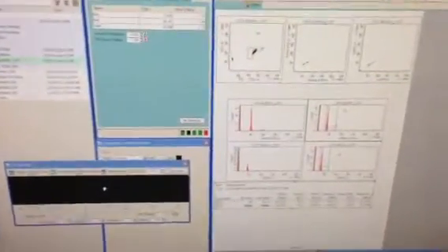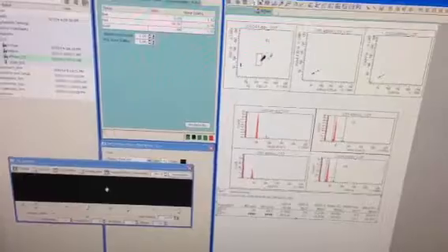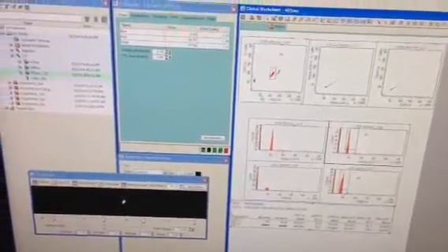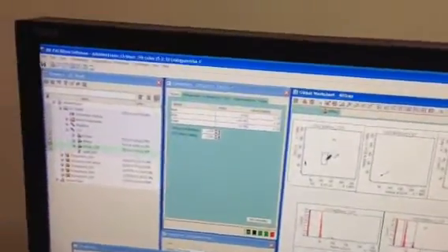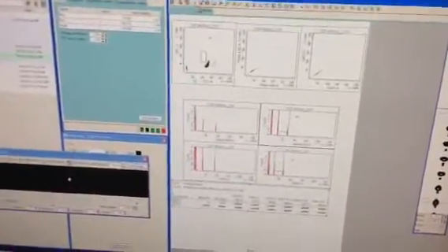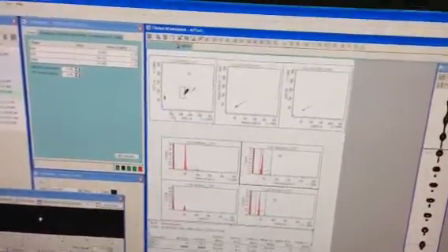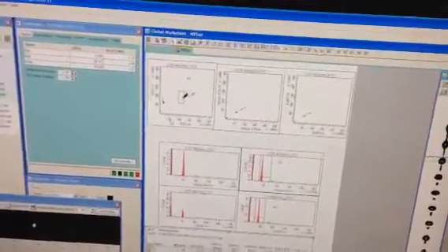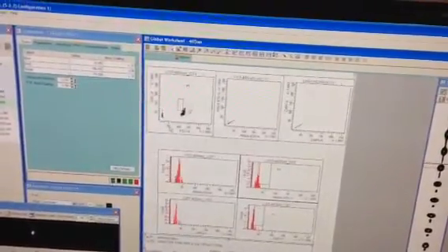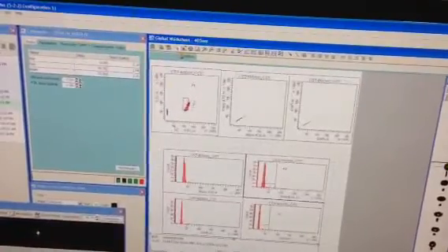Just as an example, this is where we started, where there was a little bit of a skew on the population. The DAPI channel was a little wide. And what I can show you is when I just adjusted the sweep, this one that's visible from the front of the machine, we're trying to optimize the peak of the detection. If you go too far, it goes back down again. So we just adjust it so that it's at the highest point.